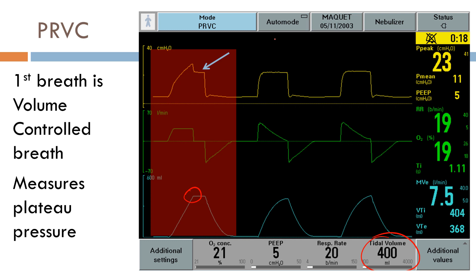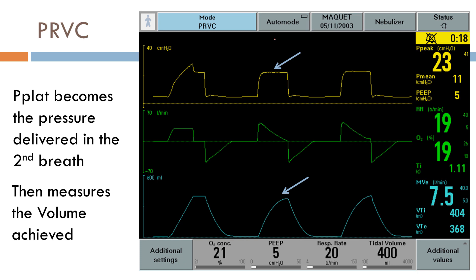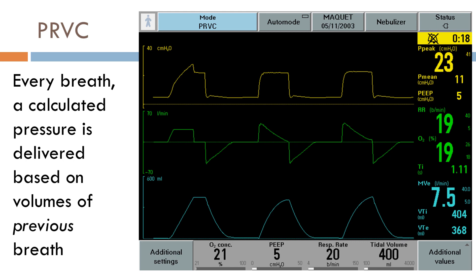Every subsequent breath from now on will be a pressure-controlled breath. So the pressure of the second breath will be the plateau pressure from the first breath, and as a result, we'll measure the volume achieved. The computer is figuring out if the volume achieved is below, at, or above our goal of 400. The pressure of the following breath will be determined based on the volume of this previous breath — every breath, a calculated pressure is delivered based off the volumes of the previous breath.